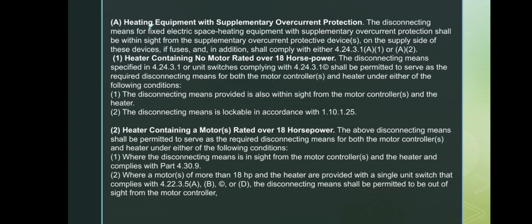First, heater with no motor over 1/8 horsepower. The disconnecting means or a unit switch may serve as the disconnecting means if it is within sight of the controller and heater, or it is lockable. Second, heater with motors over 1/8 horsepower. The same disconnecting means may be used if, first, it is within sight of the motor controller and heater and complies with Article 4.30.9, or if the heater and motor over 1/8 horsepower each, use a single approved unit switch; the disconnecting means may be located out of sight.